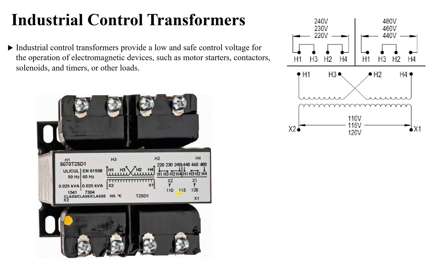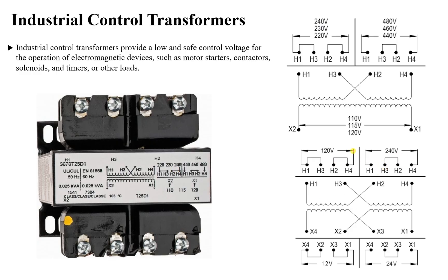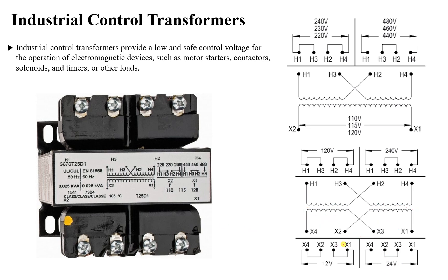This connection helps to get the same voltage for different supplies. There is another configuration that lets you control the output to get different voltages. For example, if you connect the secondary coils in parallel they give 12 volts, and if you connect them in series they give a higher voltage. If X2 and X3 are connected together and each coil is 12 volts, in series they give a higher combined voltage — providing more flexibility.